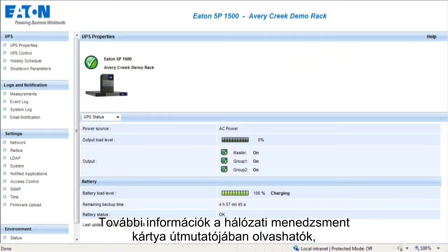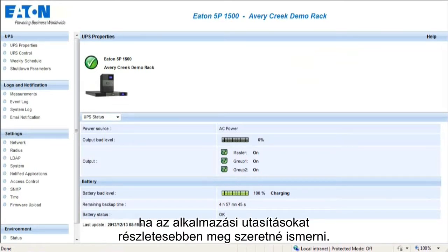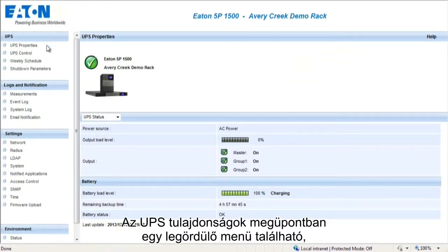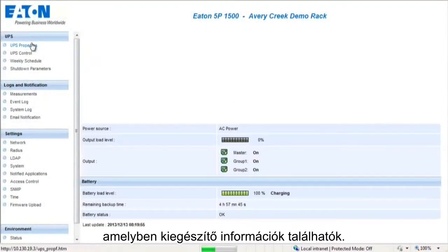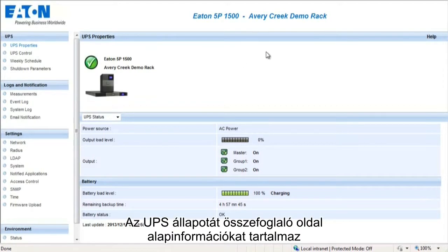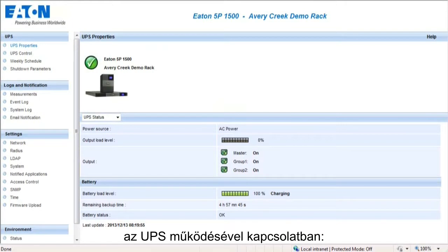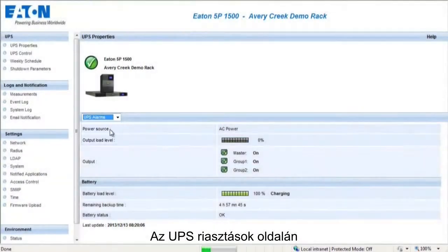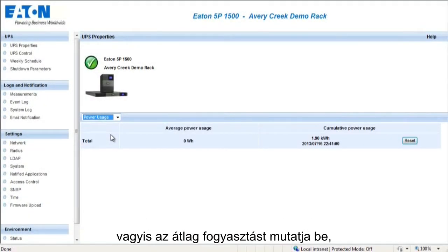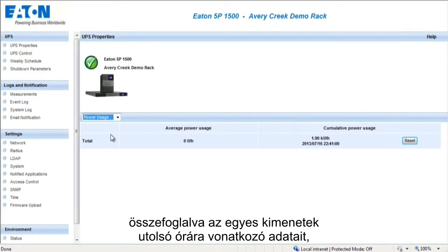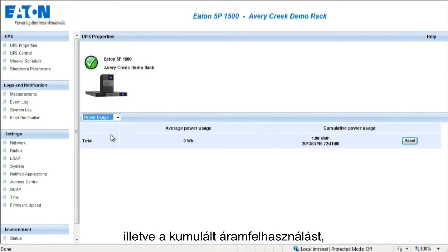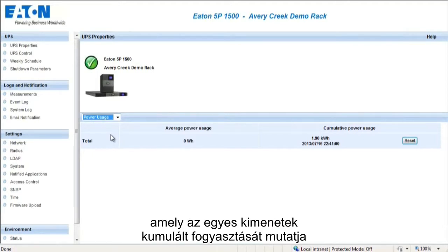Please reference the Network Management Card User Guide for detailed application instructions. The UPS Properties section provides a drop-down menu in order to view additional information. The UPS Status page provides basic information regarding the operation of the UPS, actual backup time available, and status of the battery. The UPS Alarm page displays all alarms that have been activated. The Power Usage page provides an average power usage, which is the average consumption on the last hour of each output, as well as the cumulative power usage, which indicates the consumption cumulated of each output since the last reset.